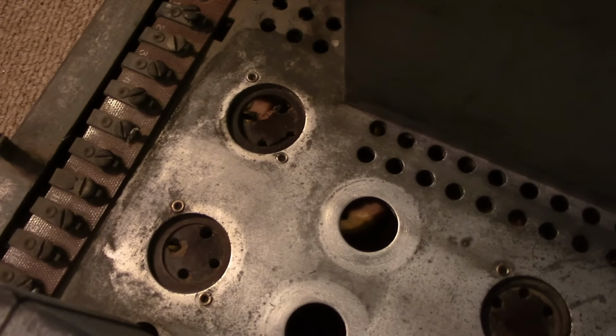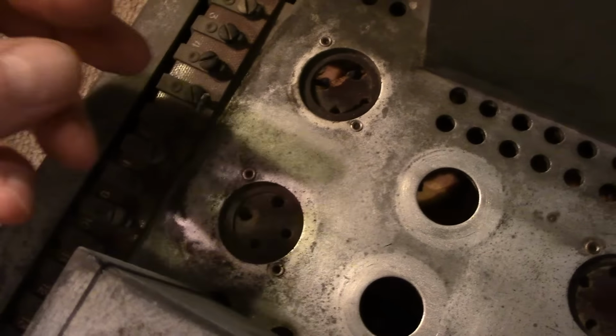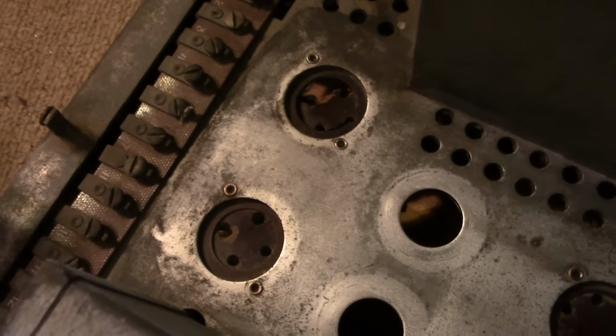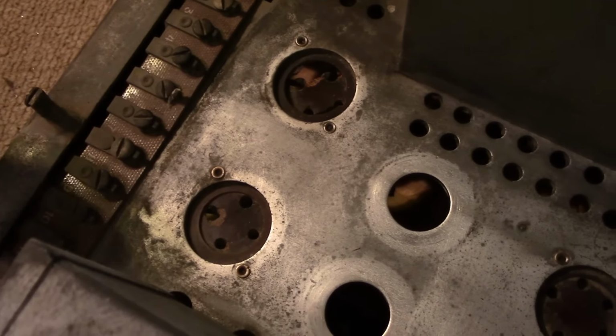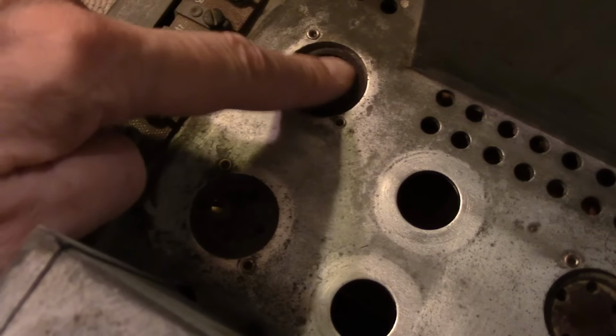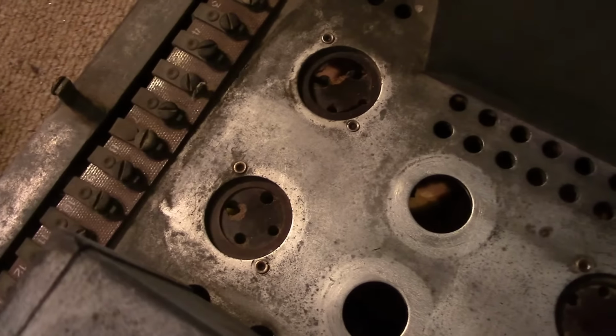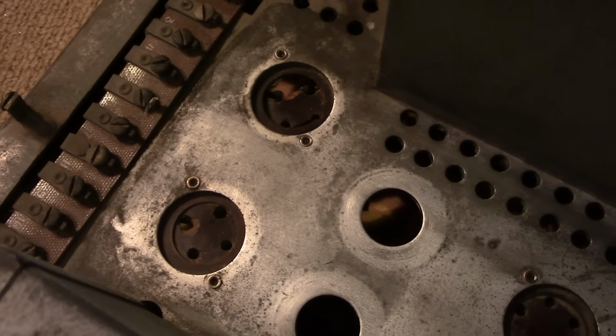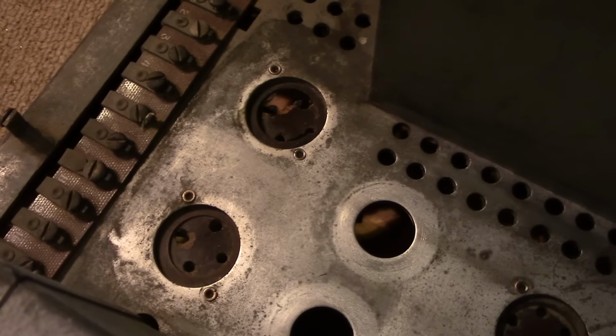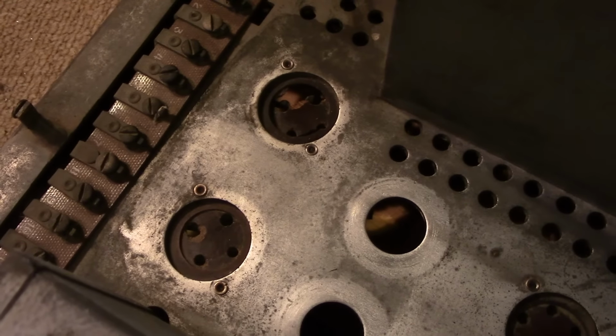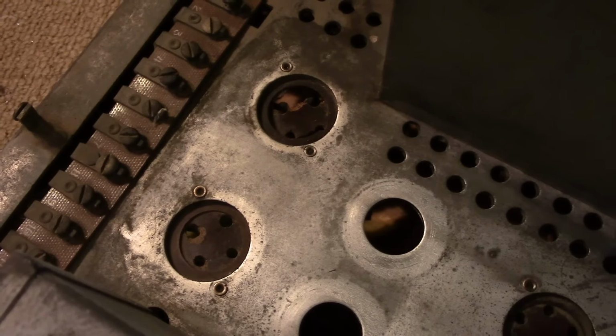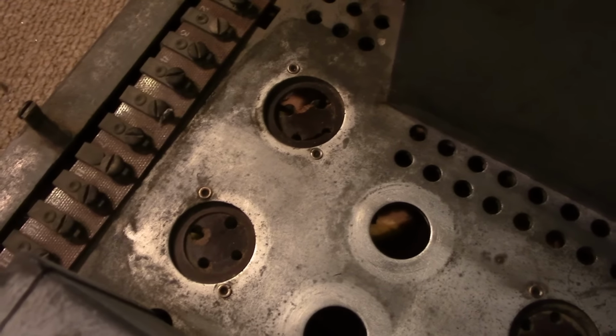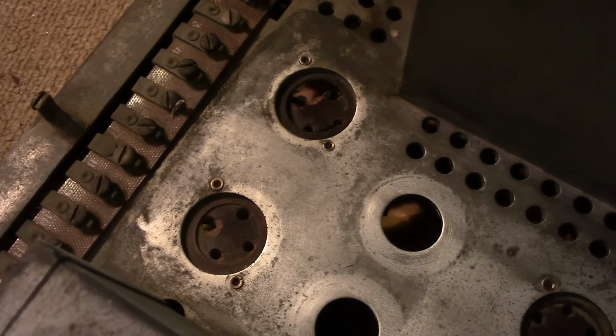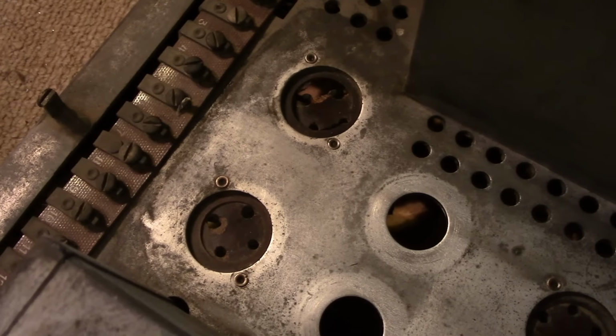The components down below that grab onto the pin are very robust—they really tightly grip the pin—but the insulating material is phenolic, and that combination of very stout metal connectors on brittle phenolic means they break from the tubes getting repeatedly replaced.